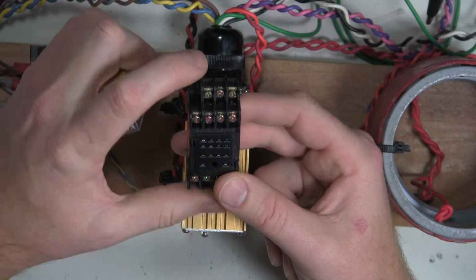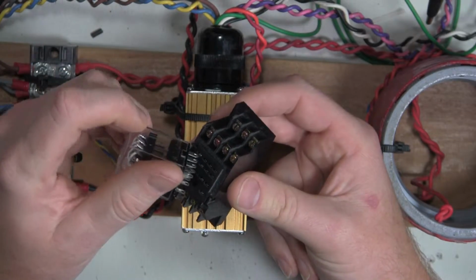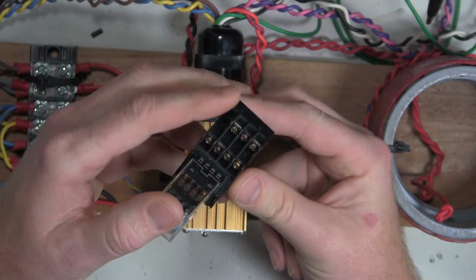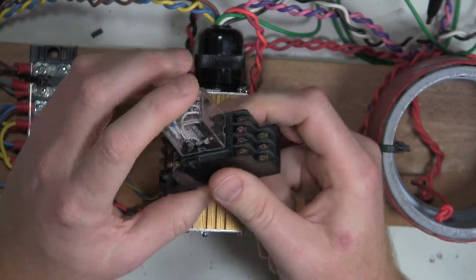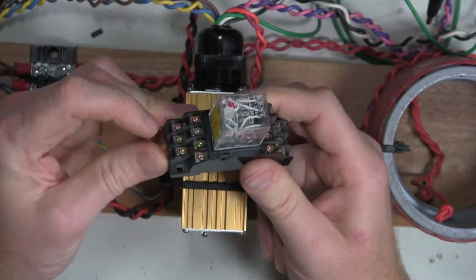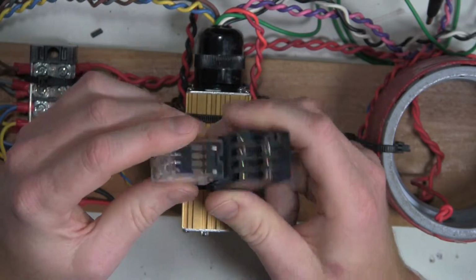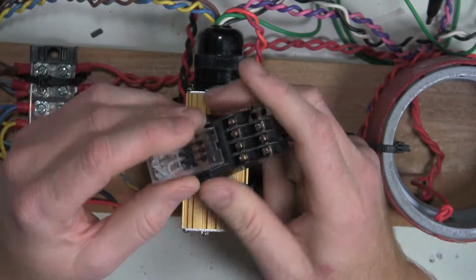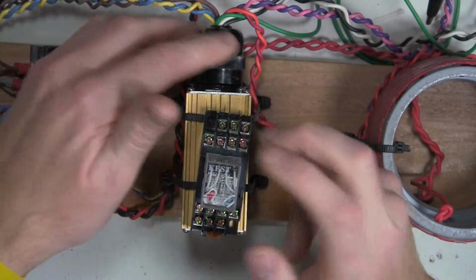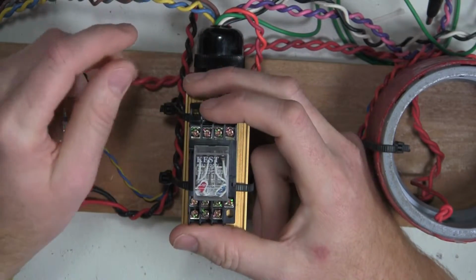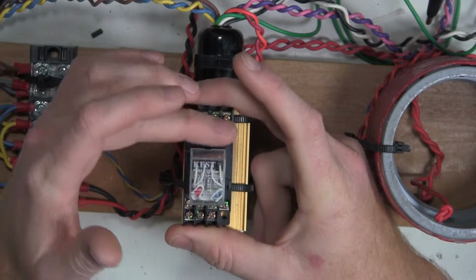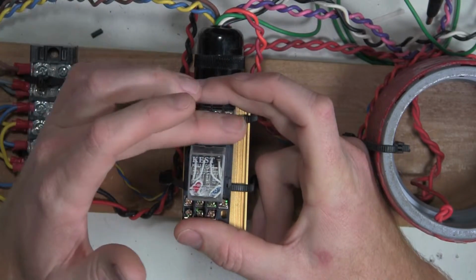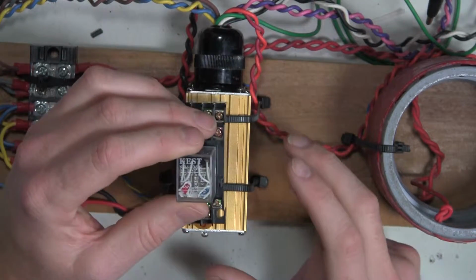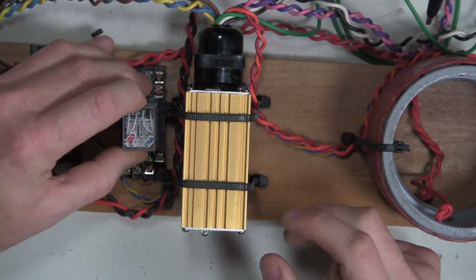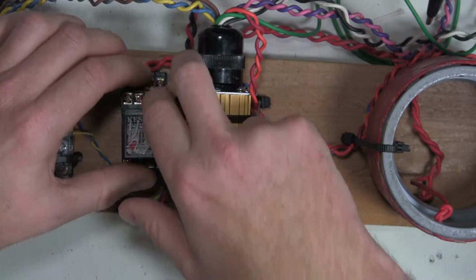Even if the loop detector's covering it, you don't want to have an interactive display with high voltage exposed, even slightly exposed. You never know who's going to be touching the display, and you don't want the liability of somebody getting shocked or hurt, much less you don't want it on your conscience for anybody to get hurt. So that's one of the reasons why I was saying you don't want to do that, or you want to have this protected some way, shape, or form if you do put it on a socket. But the thing I like about putting it on the socket is you can mount it. You can mount it right here, and then you could easily unplug and plug a loop detector in to test it.